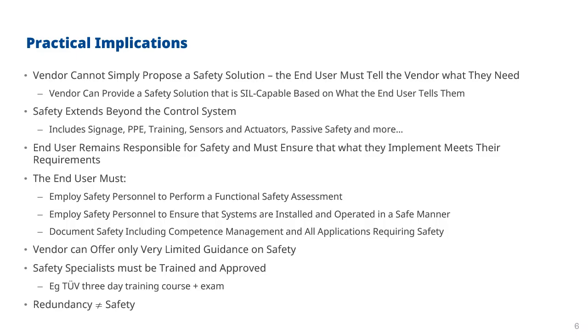And then you also need to follow all of the appropriate safety standards around whatever industry you're working in. Another point here that a lot of people get confused about, redundancy is not the same as safety. You can have a safety system that is redundant, but you can also have a safety system that is operating in simplex mode. The safety comes from the design and qualification of the system itself, not just from having redundant components. And the opposite is also true. Just because you've got a redundant system, it doesn't mean it's a safer system. It might give you higher availability and it might be more reliable in operation. But if it fails, it might fail to the wrong state, leading to a non-safe situation. So redundancy is not the same as safety, and vice versa.